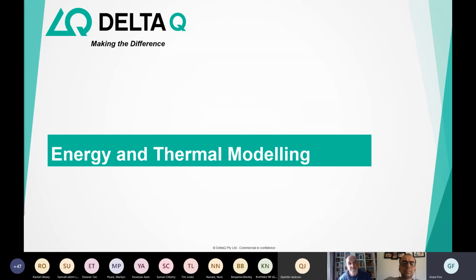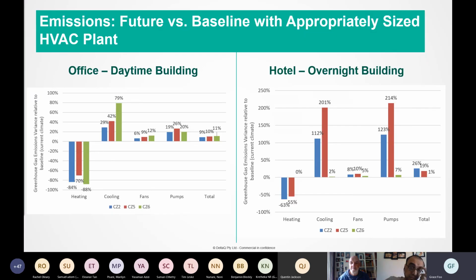So again, quickly, we're going to wrap up soon, but I'm going to run through what our energy and thermal modeling results were. When we use DesignBuilder to simulate the differences between using a future climate file versus a baseline climate file, remember future is 2050 in this context, we found that in an office building, if we size our HVAC plant appropriately, meaning we've used the future climate file to size the HVAC plant rather than our baseline climate file, heating greenhouse gas emissions decrease by close to 80 to 90%.